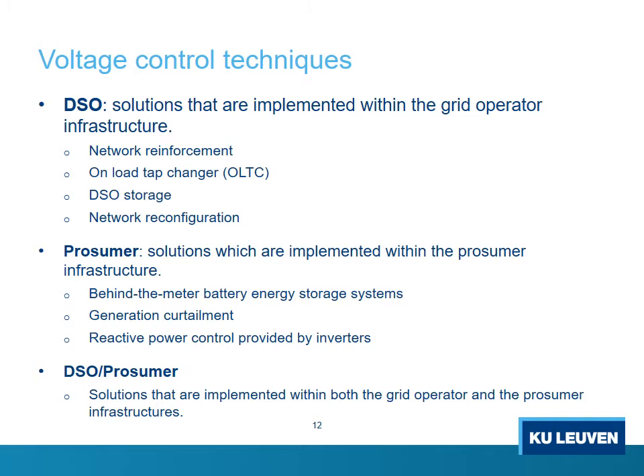Storage owned by the distribution system operators that can be charged during the day when the photovoltaic generation is high, and it can be discharged during the evening when the consumption is high. Network reconfiguration: let's say there is a high reverse power flow in phase A and low reverse power flow in phase B and phase C. What you can do is use a normally open switch, close it, and let part of the current flow from phase A to phase B and phase C. That is to reduce the high reverse power flow in phase A, that is, to mitigate voltage rise in phase A.